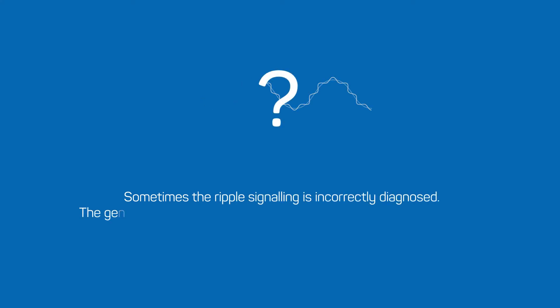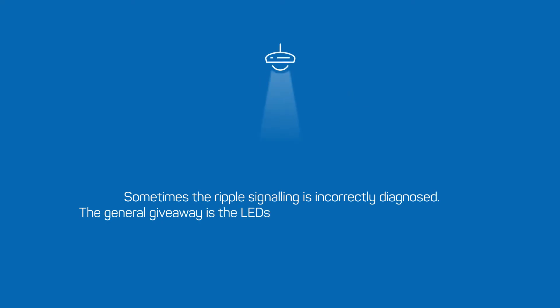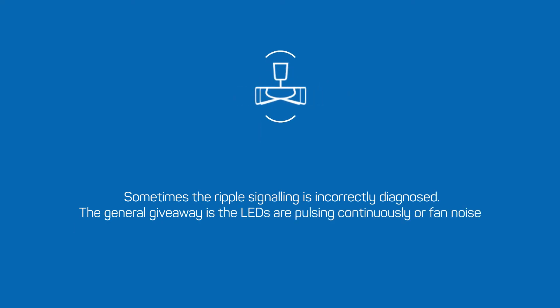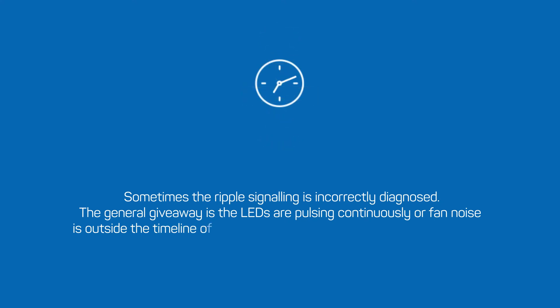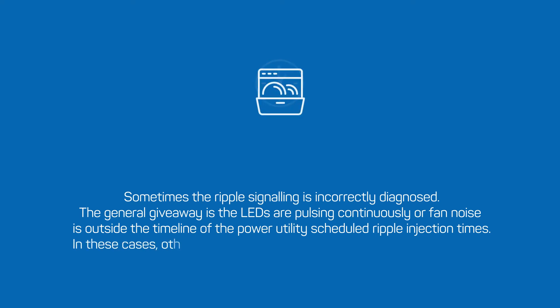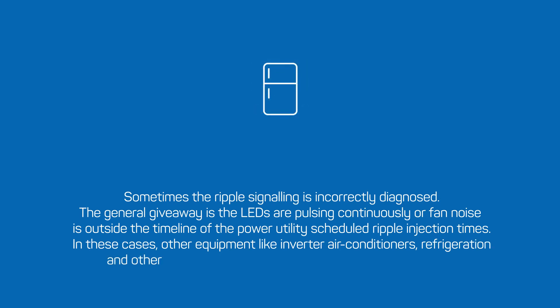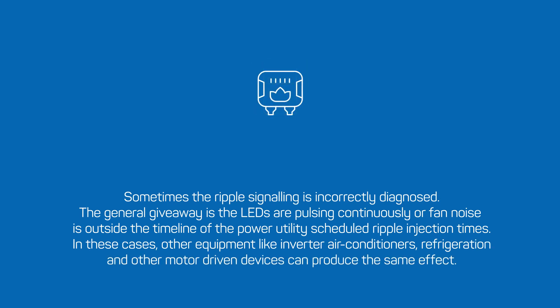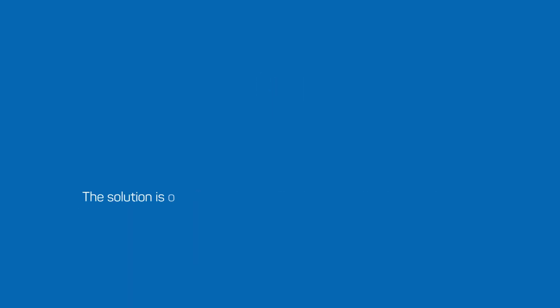Sometimes the ripple signaling is incorrectly diagnosed. The general giveaway is that the LEDs are pulsing continuously or fan noise is outside the timeline of the power utility's scheduled ripple injection times. In these cases, other equipment like inverter air conditioners, refrigeration and other motor driven devices can produce the same effect. The solution is our main surge and active filter products.